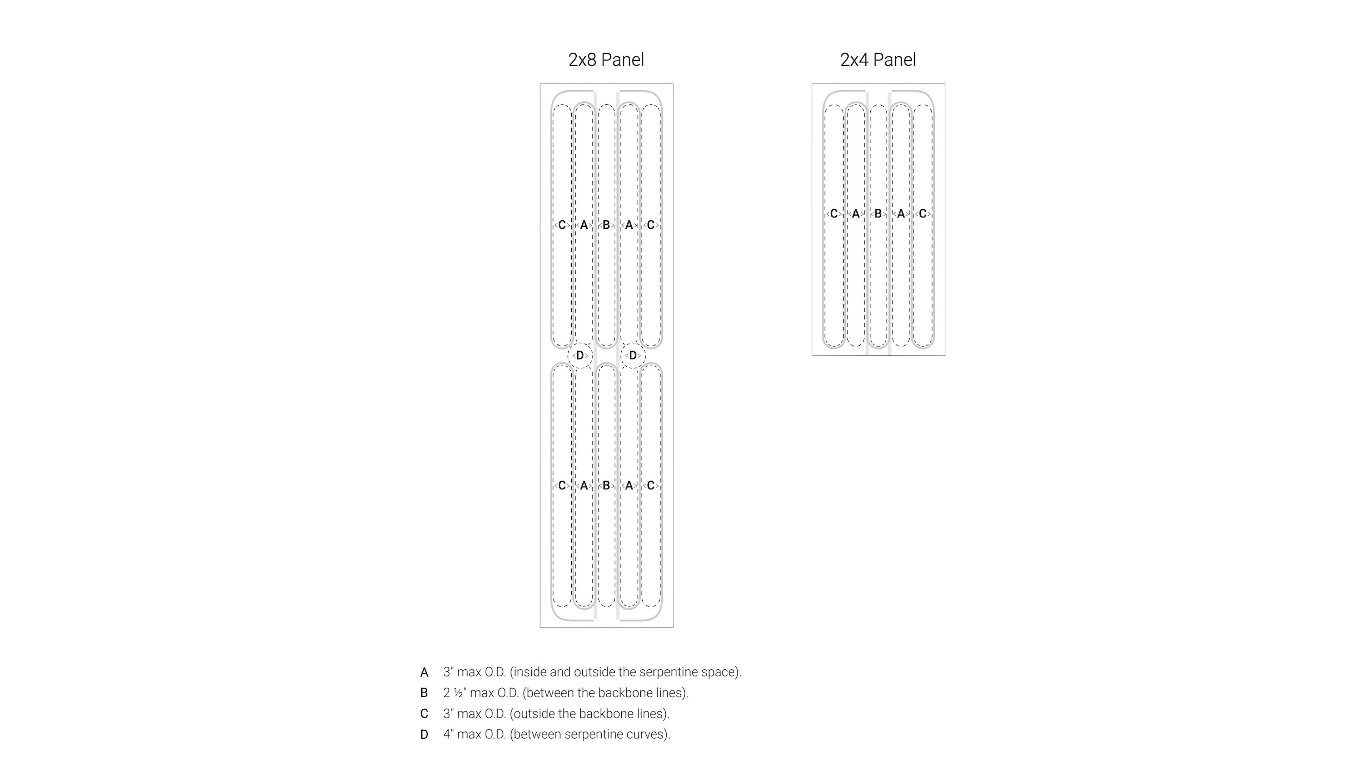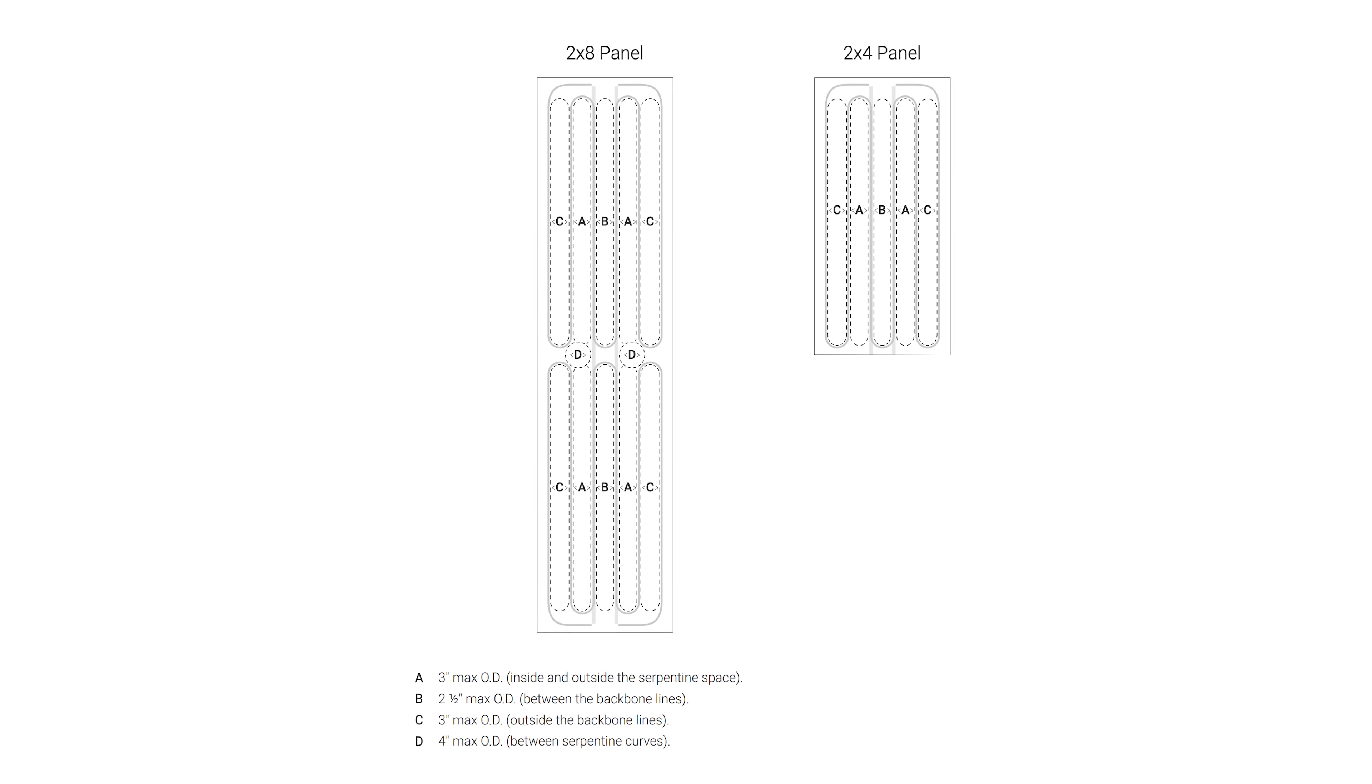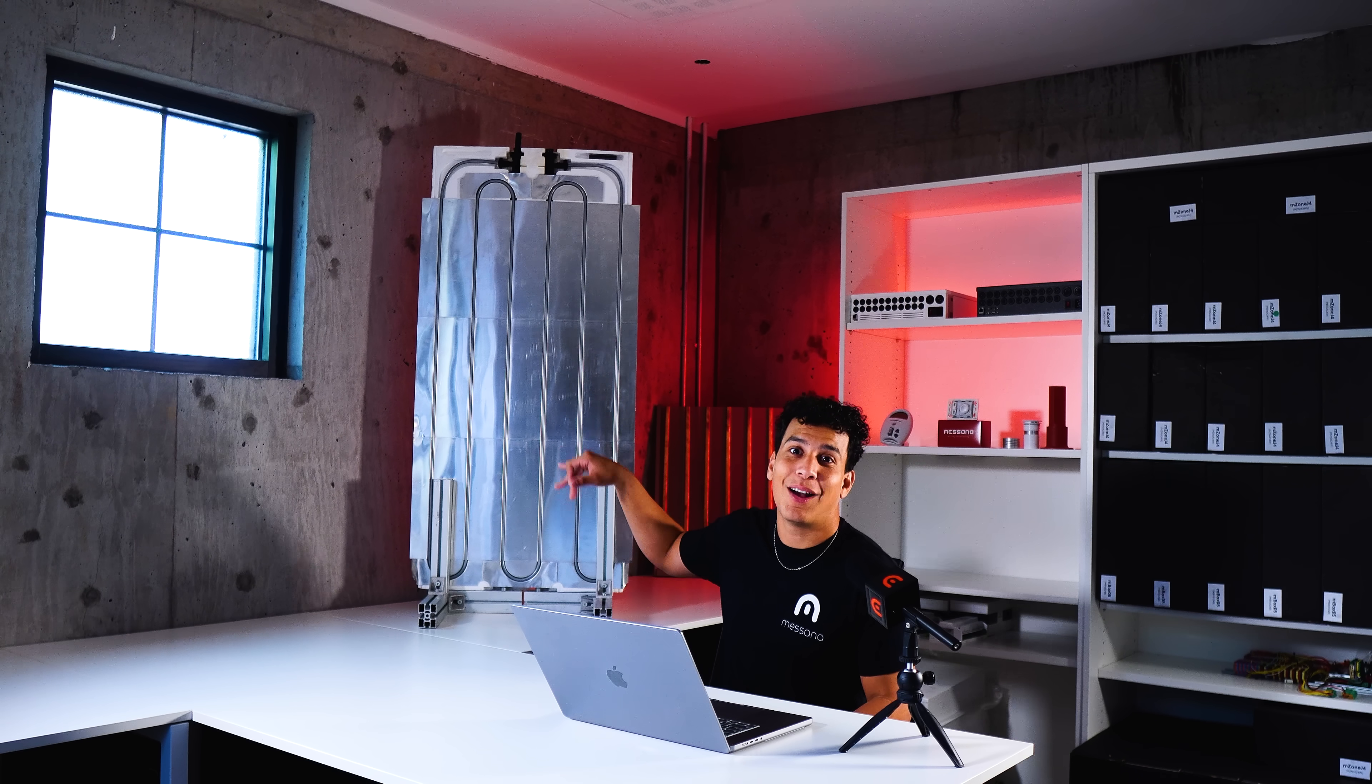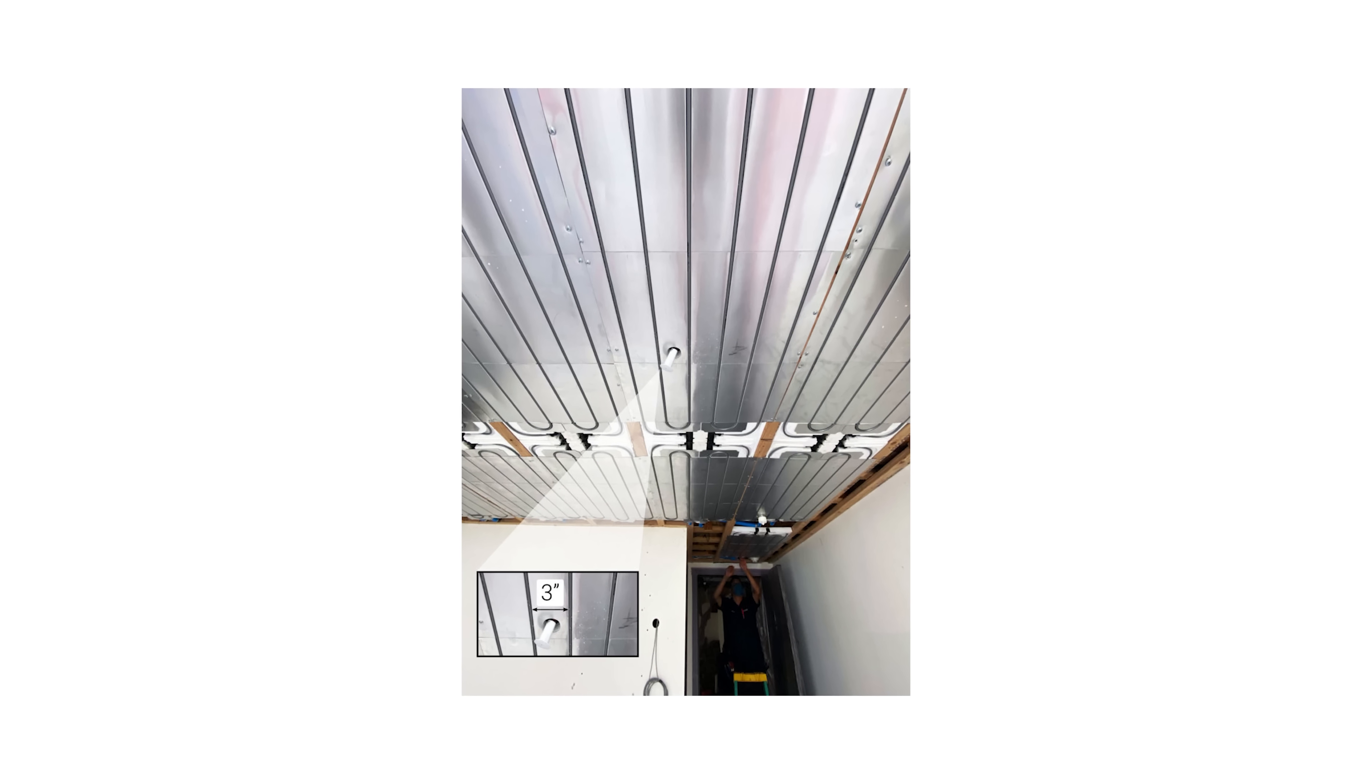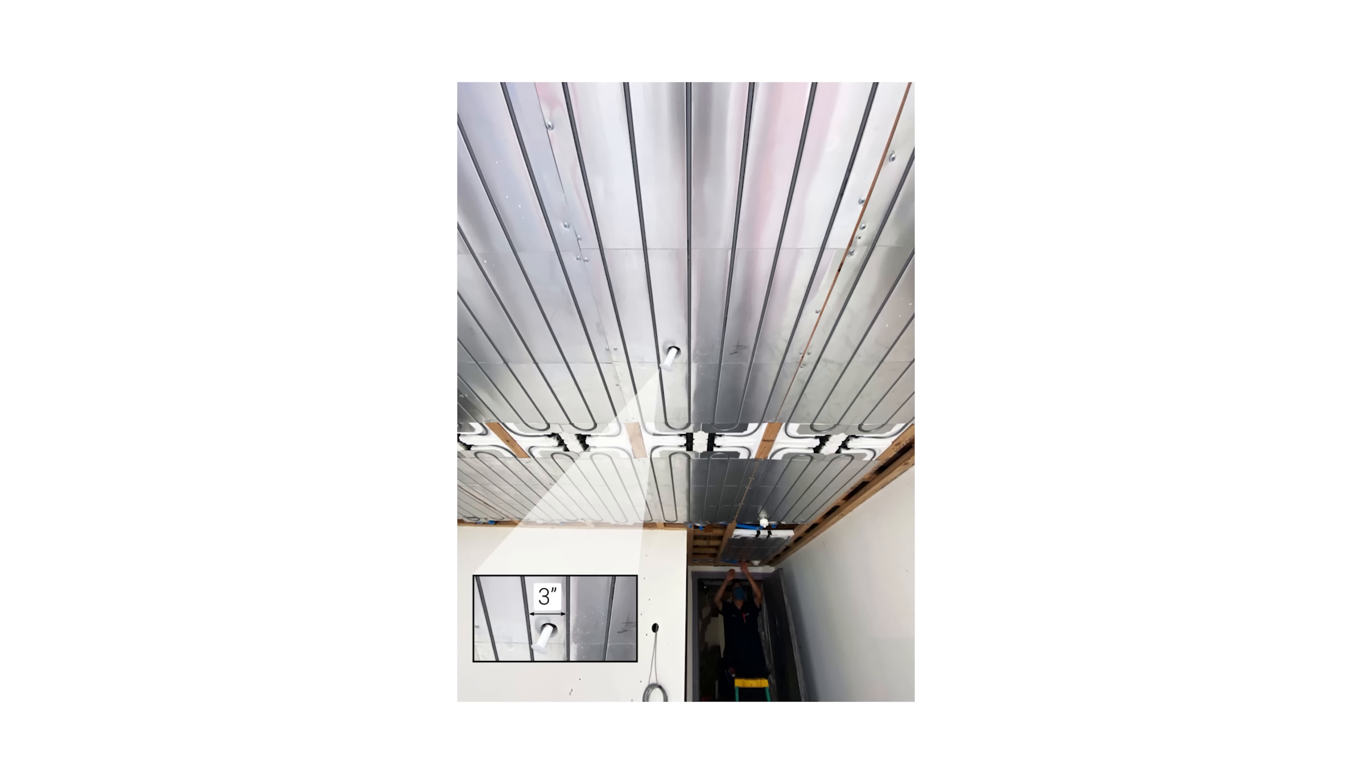There are places on the panel where you can put a hole, about two and a half inches up to four inches. Depending on where you're placing that hole in the panel, you can put holes in them. We just make sure that you avoid the hydronic piping so you don't have any leaks. We can typically work around ceiling fixtures in the design phase, as well as put holes in the panels to incorporate them later or during construction.